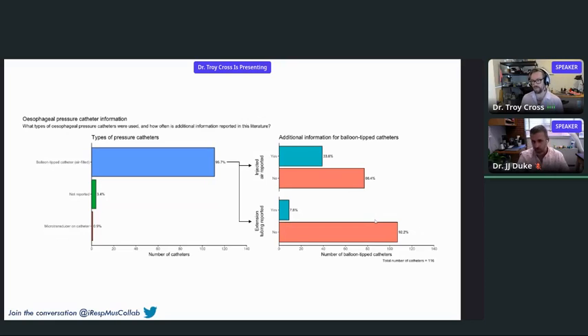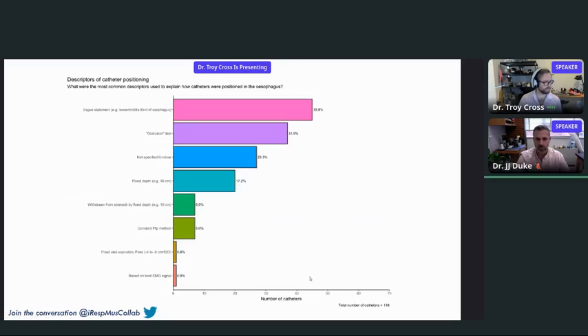I feel it's important to state that no extension tubing was used, as much as it is to be clear on when it is used, because that gives me the ability to evaluate whether the pressure catheter was compromised by potentially a poor frequency response from the addition of extension tubing, therefore skewing your results a bit.